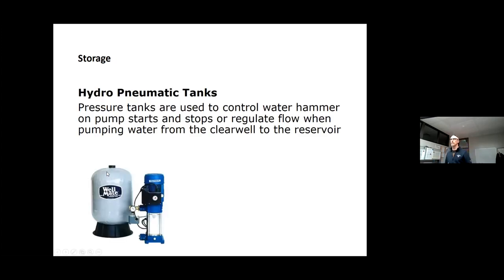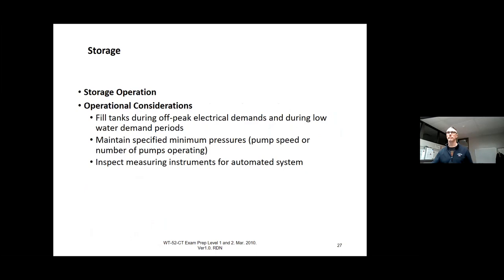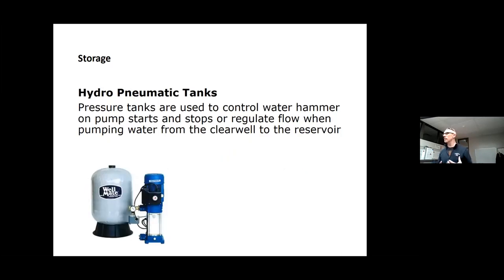Smaller well systems will use something called a hydropneumatic tank — basically a small version of a reservoir. A well pump will pump to this tank, which provides service to your customer. When the pressure gets low enough it triggers the pump to come on and re-pressurizes the tank, then the tank provides service — it works really well. One thing about these: make sure they're clean. They usually have a rubber bladder inside, and over time especially with chlorinated water, this will deteriorate, so you've got to make sure they're always maintained.